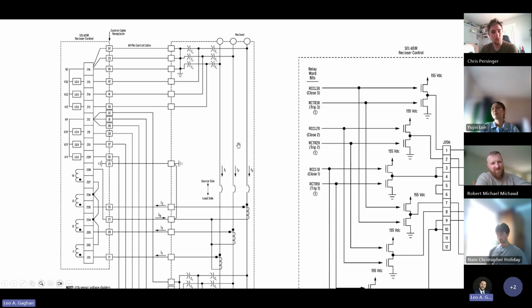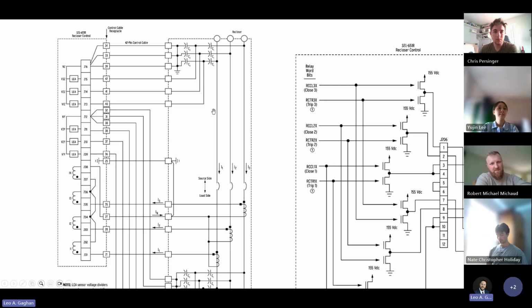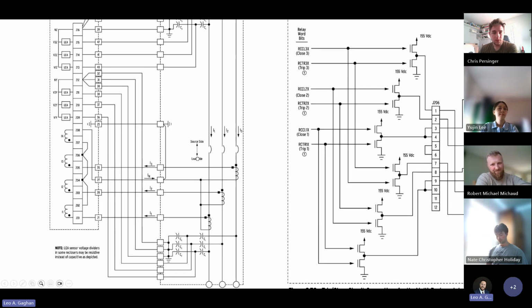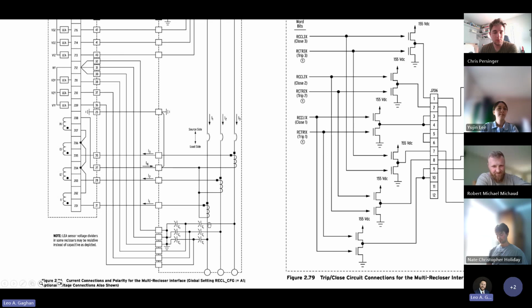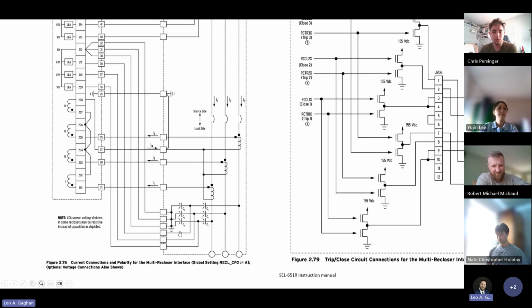So for the recloser, it looks like this one has two PTs, one on the source side and the other on the load side. And these PTs are called low energy analog PTs. Really all it is, right, is you've got two capacitors and you grab that middle point to get a voltage.